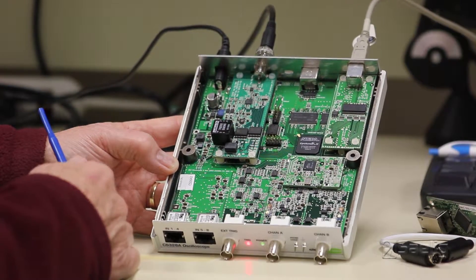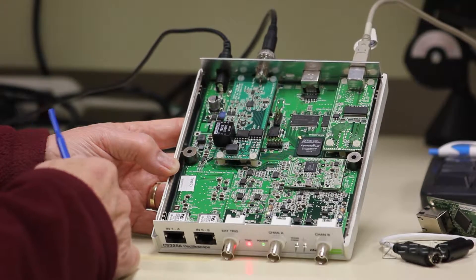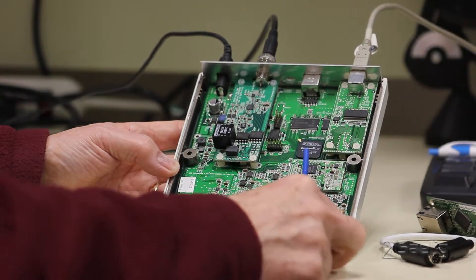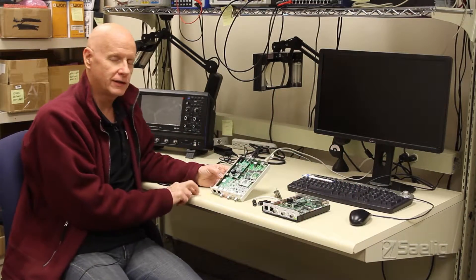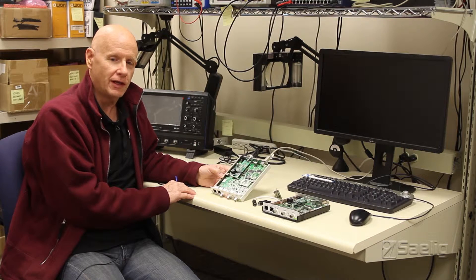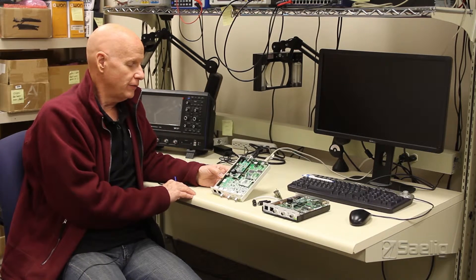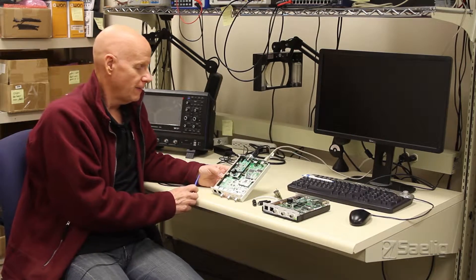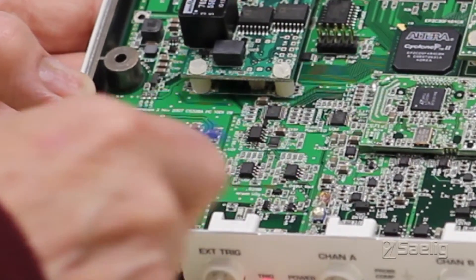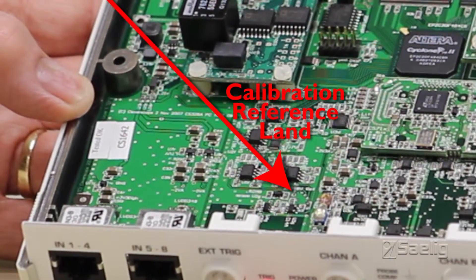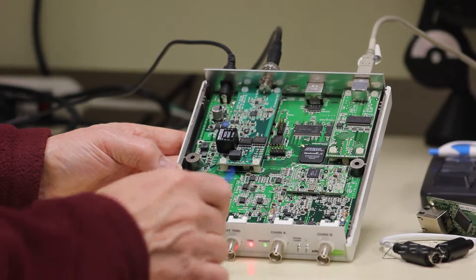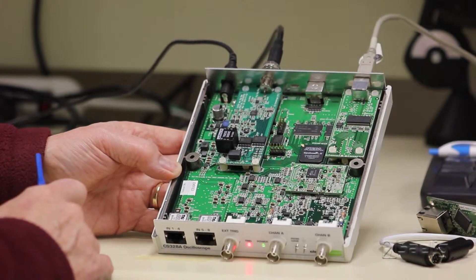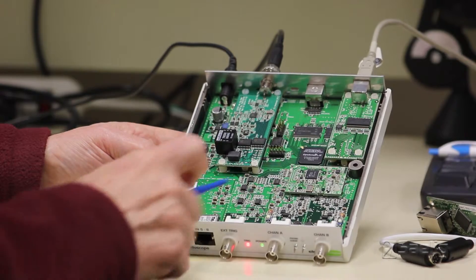A couple more points. One of the things is that the CleverScope can have its calibration checked by you on an annual basis using a calibration reference source, which is a small land right there which is marked. When you want to run that annual calibration, you will have to access that point and follow the instructions in the application on the screen.